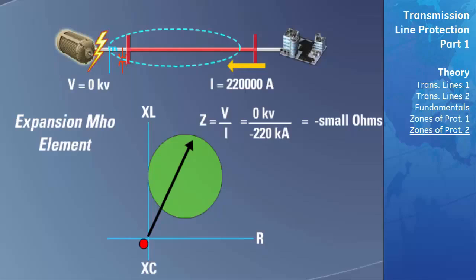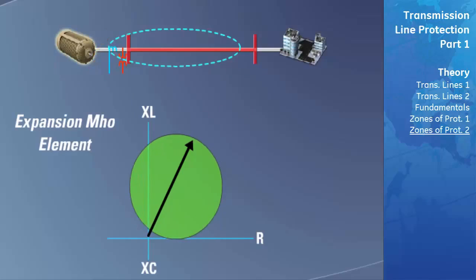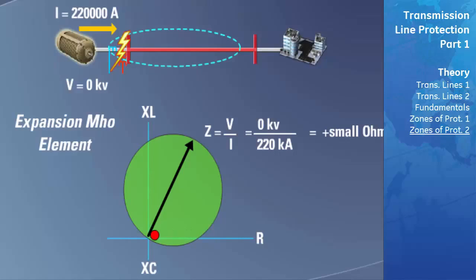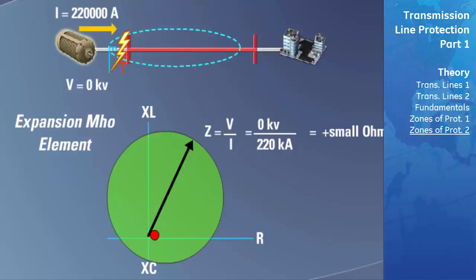Notice, however, that the reach of the Mho circle did not change and still extends out to the end of the original zone of protection. If a fault occurs just after the beginning of the transmission line, current will flow into the CT from the positive direction and the calculated impedance will be positive, plotting very near the origin in the positive direction. To make sure the Mho characteristic does recognize this as an internal fault that needs to be cleared, the relay recognizes the low positive impedance and enlarges the radius of the circle. Since the Mho circle now extends past the origin to include a larger area, the location of the fault is sure to fit in the zone of protection and the fault can be cleared properly. The reach of the Mho circle did not change and still extends out to the end of the original zone of protection.